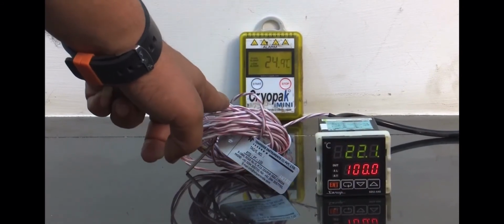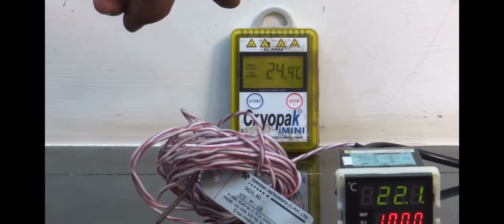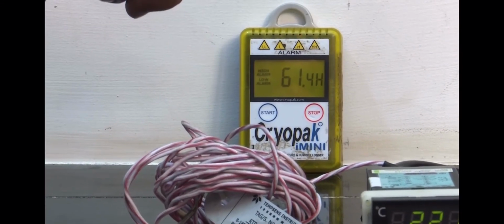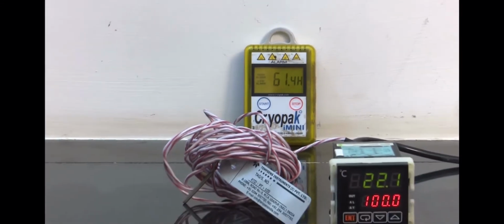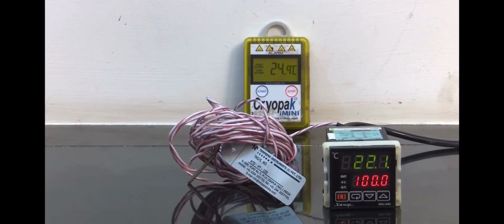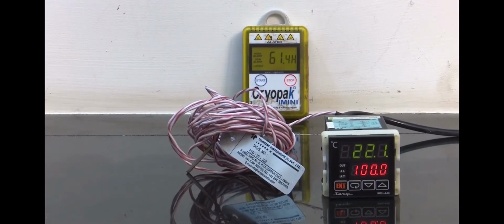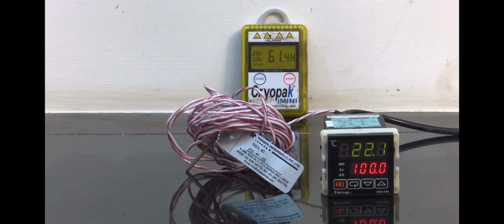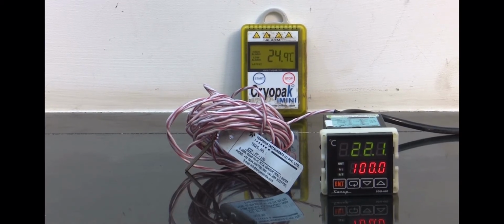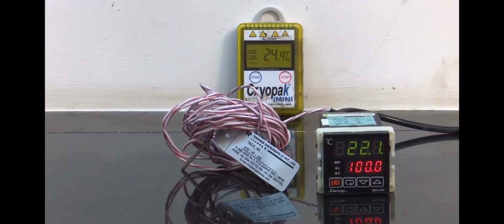Keep the controller with sensor for at least 30 minutes for soaking at 25 plus minus 3 degrees centigrade so that the temperature is brought to equilibrium. Before starting calibration, ensure that the environment condition is maintained. The temperature should be between 25 plus minus 3 degrees centigrade and humidity should be 45 to 75% RH.